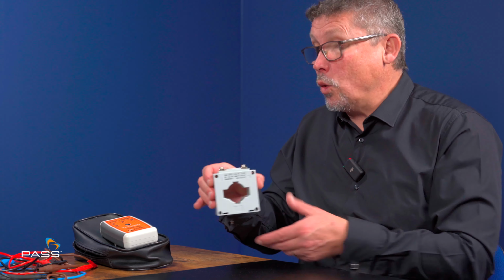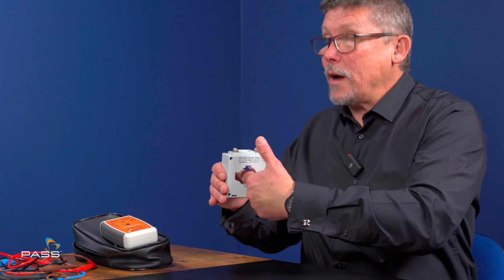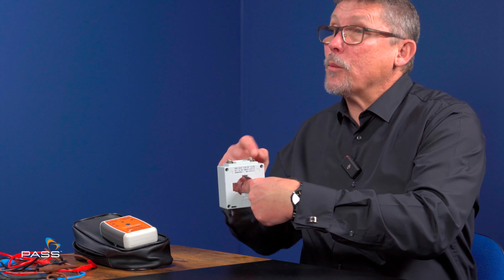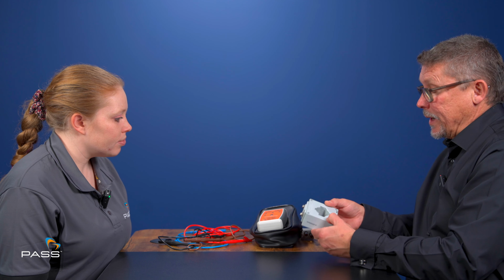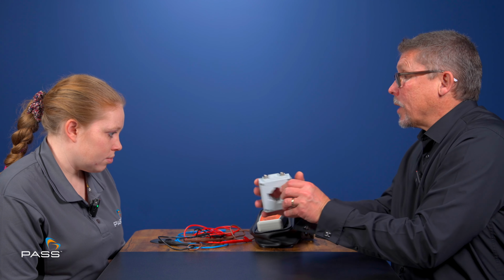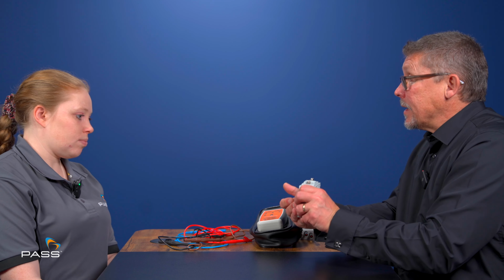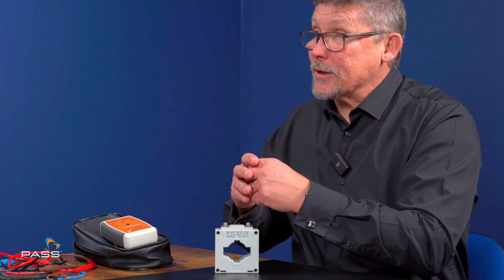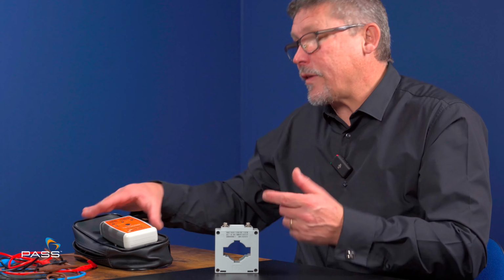Literally all we're concerned with is if we put the wire through that way, which one is now positive. In a case like this, you can see it's actually labelled S1, S2, so it's very easy to do. But very often, particularly in the old days, you'd literally have a hand-wound coil around a magnet with two terminals at the top, and you'd pass your cable through without knowing which one was which. So that's where these come in.